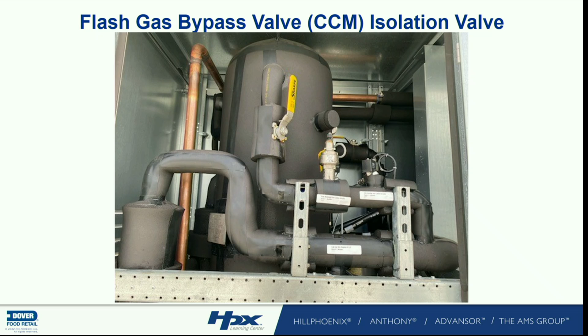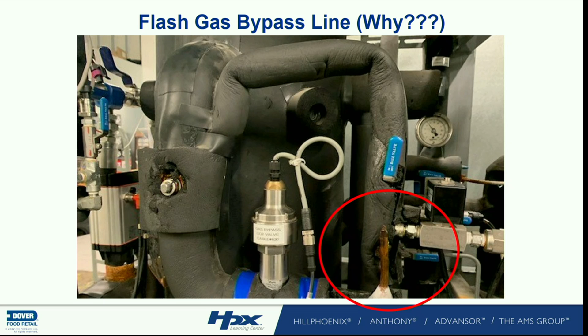If it's going too low, what would I close? Anybody got any idea? Ball valve. I can start throttling it, or to prove it I can just close it and see if the pressure jumps up, or I can actually regulate through there. Or if I happen to have a bypass valve, I can regulate it through the ball there. There's no reason at all for that receiver pressure to be stuck because that valve fails, yes? You can use your gauges, you can use that valve, use the tools you already have and simply drive them. Are we good? Does anybody see a problem with this?